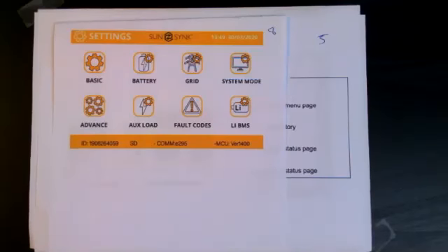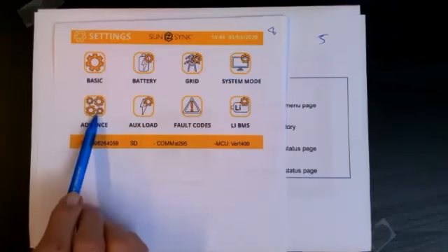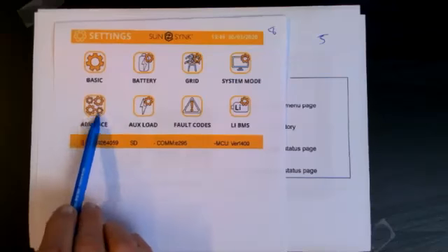I've seen it in the UK once. I've seen it in South Africa about 20 times, where people have stolen a neutral cable because they felt it's the safest wire to steal. And then suddenly the three phase creates its own neutral, but the neutral can reference off another phase, and therefore the voltage on the phase that you're picking up can rise massively or decrease. So it's quite dangerous. Advanced settings, I'm not going to go through now.